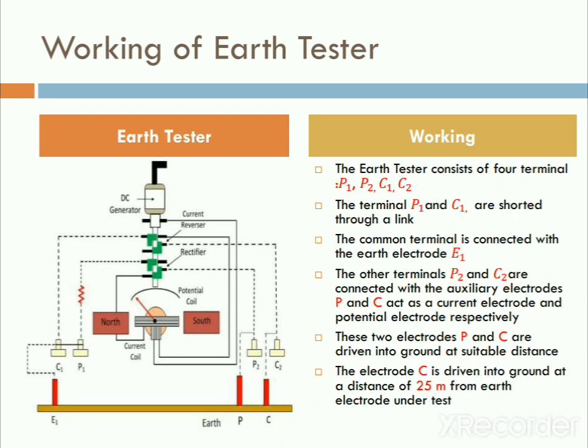The electrode C is fixed in the ground at approximately 25 meters distance from the earth electrode under test. Then the working process begins with terminals P1, P2, C1, and C2.